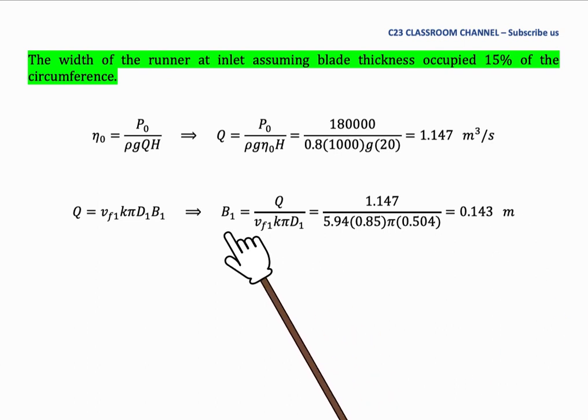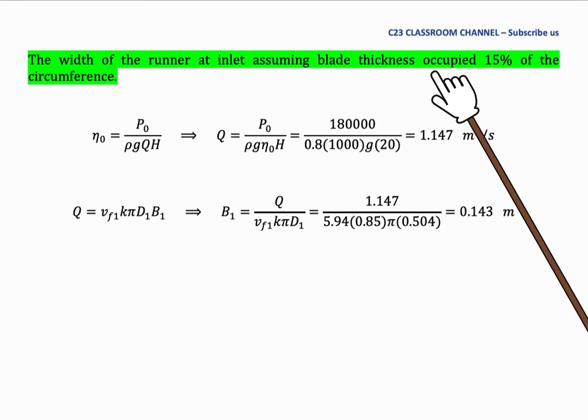To calculate the blade width at inlet, we use this equation. We rearrange and get B1 equal to Q over VF1 K pi D1. We substitute all the values and make sure the value of K is 0.85 because blade thickness only occupies 15 percent of the circumference.